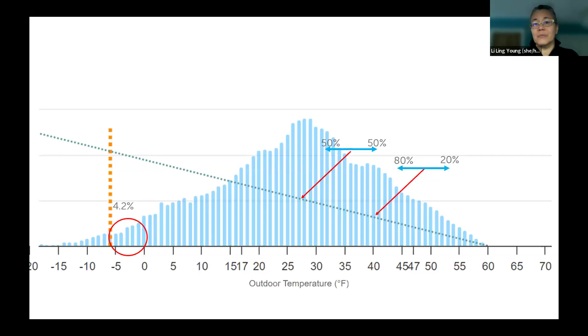Now, we already know that cold climate heat pumps lose efficiency and capacity when it's really cold. But look how many BTUs we're expending when it's really cold - not that much. And so this area where we're using the most amount of energy, it's really important that we have our equipment operating well during those conditions. So this is what part load performance is. Part load efficiency is about how efficient our equipment is when we aren't at 0 degrees, -5 degrees, or -20 degrees.